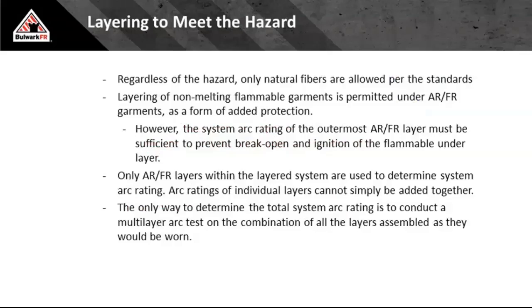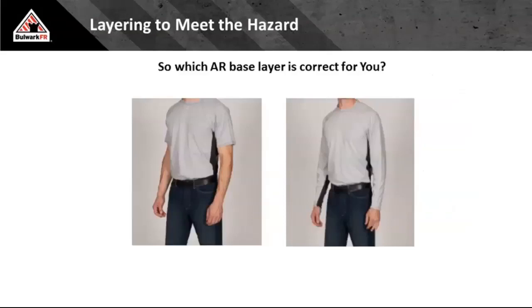Can we do better in the standards? Absolutely. Now, if you're looking to have a systems approach, meaning I want to get more protection than my single layer shirt gives me, then there are some caveats you need to understand, and we'll walk through those. So in 70E, if I just want an additional layer of protection, then fine. I have an 8-cal shirt on. I put on my 5-cal base layer. I'm going to be more protected.